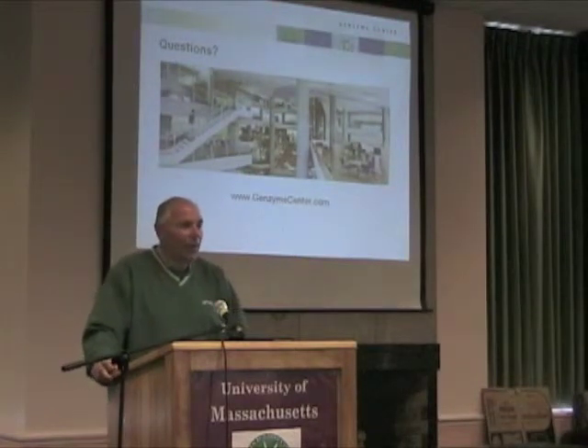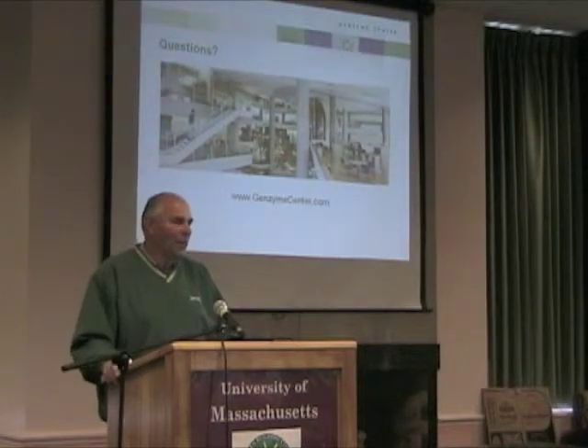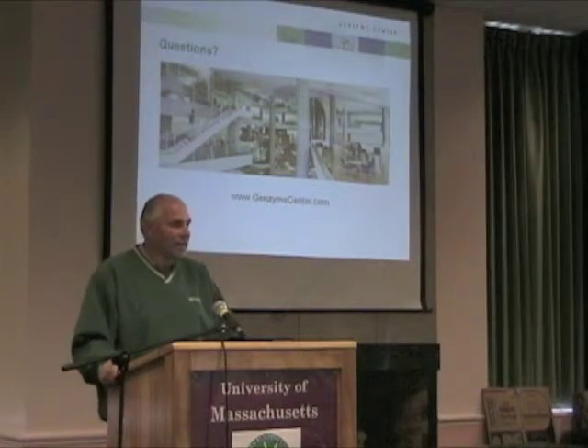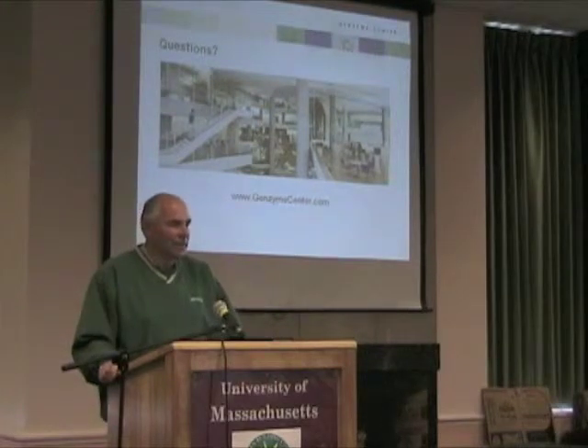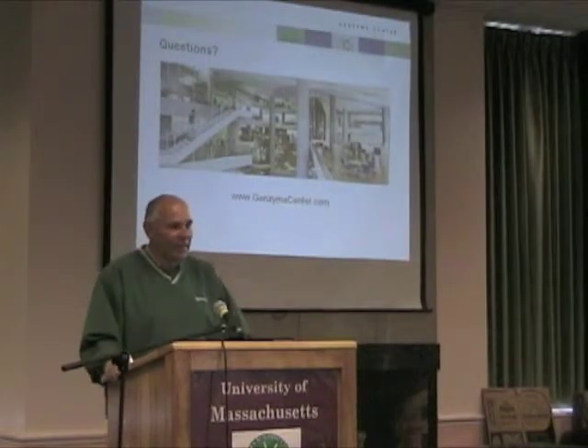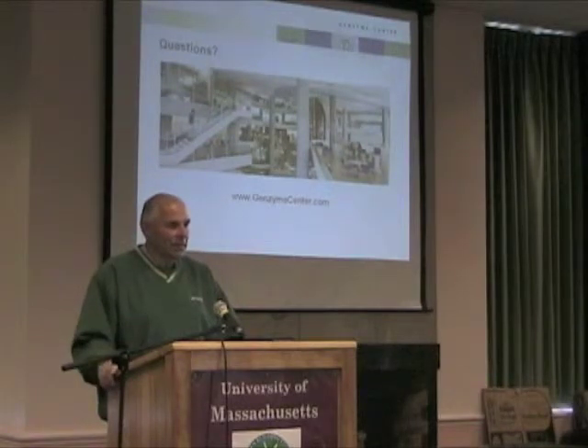Very good. One of the green points is that you have to have each individual control their own thermostat, windows, blinds, and we do have that capability. Each person can sit in their office at 46 inches out and look out the window. It's one of the criteria. But they can control their own thermostats, their own blinds, and their own lights to a point. We have the smart sensors that go between 68 and 76 degrees. After a lot of emails back and forth and girls screaming, we maintained the building at 74 degrees. But at 10 o'clock at night, even if you set it for 65 or 76, it goes back to 74 degrees. And same thing with the blinds.